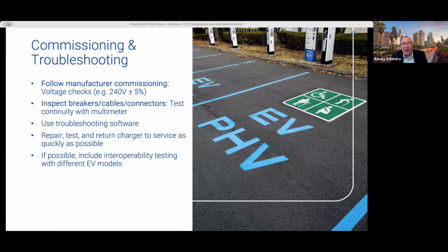First, you'll want to follow the manufacturer recommended commissioning steps. Start with voltage checks of the chargers, ensuring that you have a stable 208 volt or a 240 volt measurement that are plus or minus 5% to confirm that the charger connections are solid. Next, inspect breakers, cables, and connectors. Use a multimeter to test continuity, checking for faulty breakers or damaged cables that could disrupt power delivery to vehicles.